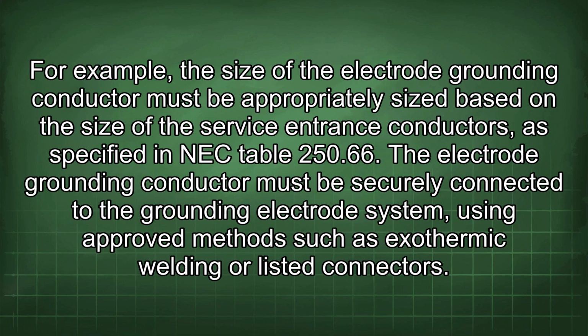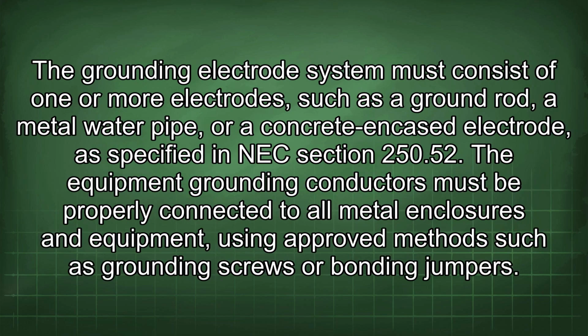For example, the size of the electrode grounding conductor must be appropriately sized based on the size of the service entrance conductors, as specified in NEC Table 250.66. The electrode grounding conductor must be securely connected to the grounding electrode system, using approved methods such as exothermic welding or listed connectors. The grounding electrode system must consist of one or more electrodes, such as a ground rod, a metal water pipe, or a concrete encased electrode, as specified in NEC Section 250.52.